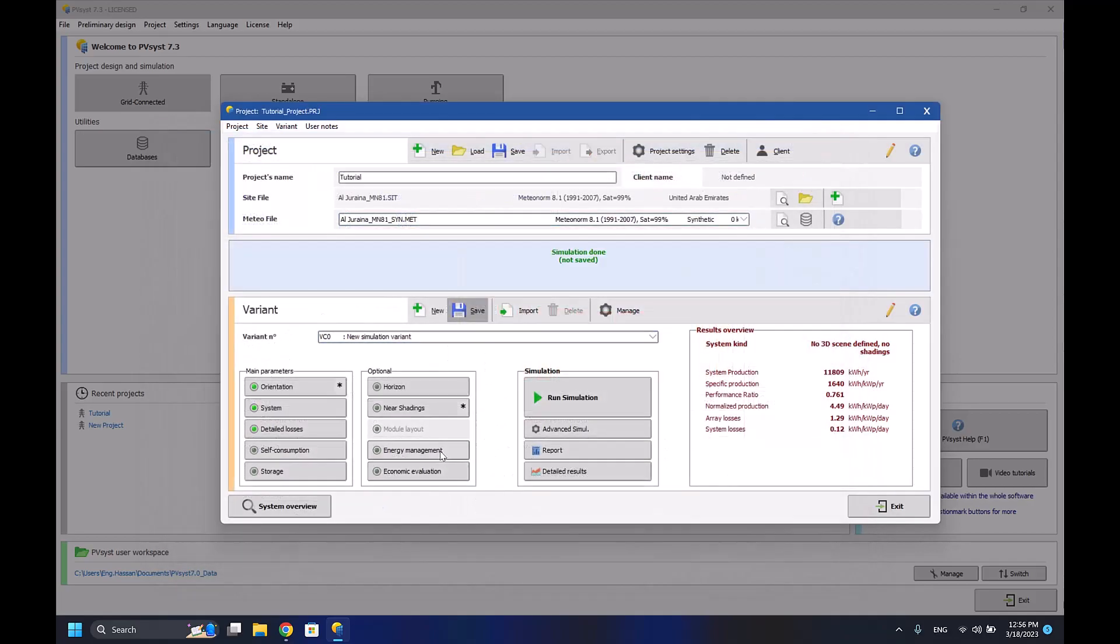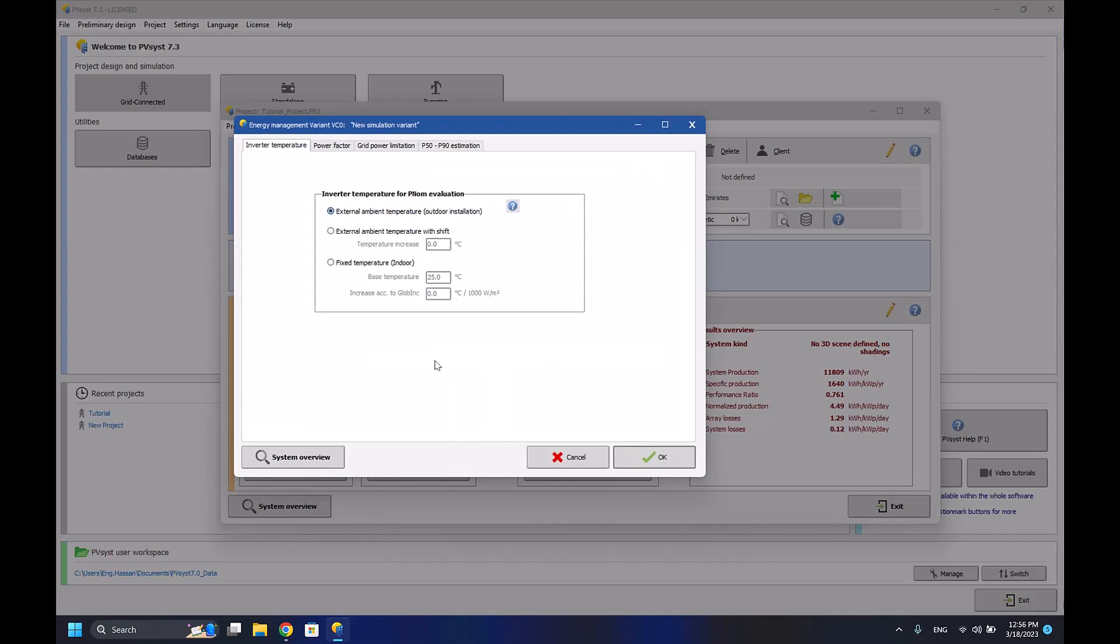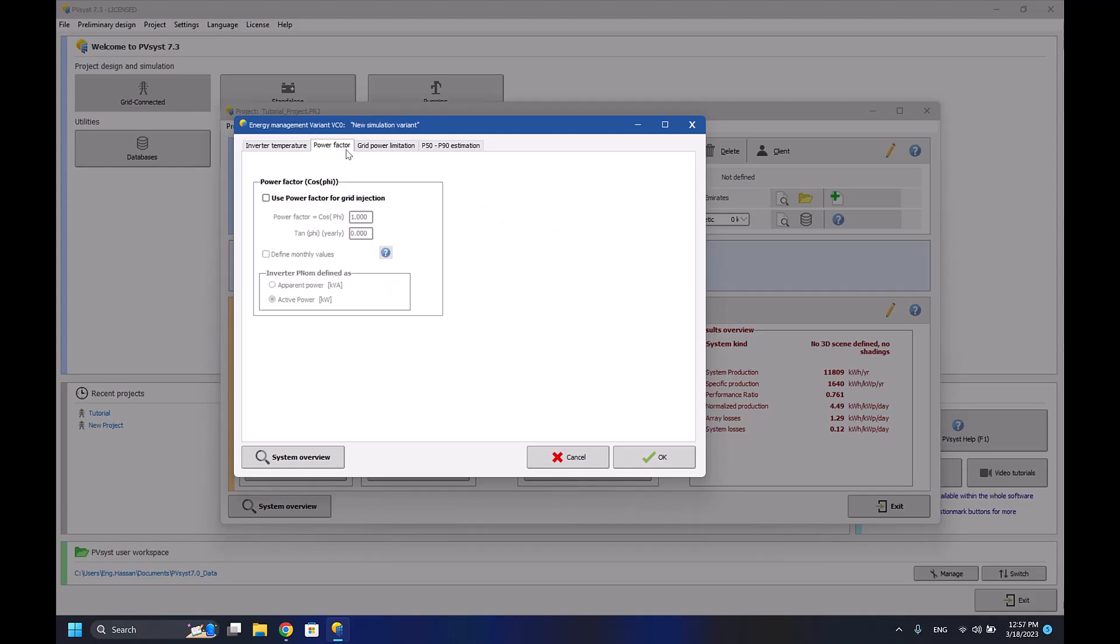Now I'll go to the energy management section. In energy management here, you can define the inverter temperature - external ambient temperature. So if you want to make it dependent on the external temperature or with shift, you can add an increase of temperature. So for example, if the ambient temperature is 35 degrees Celsius, you can add an increase of 5 degrees Celsius extra, maybe from the heat generated by the inverter itself.